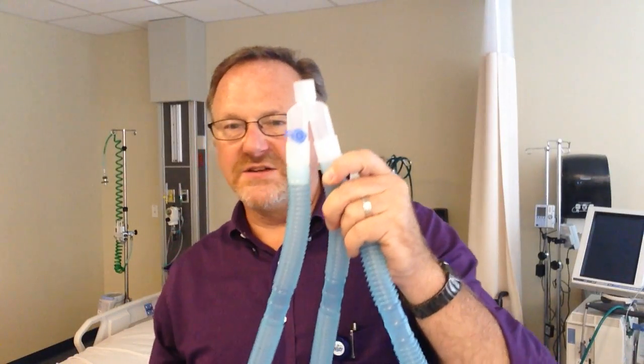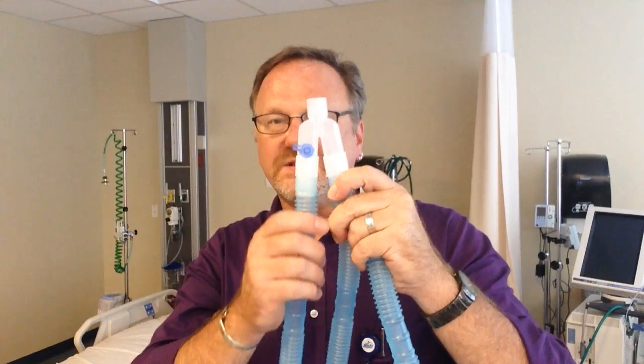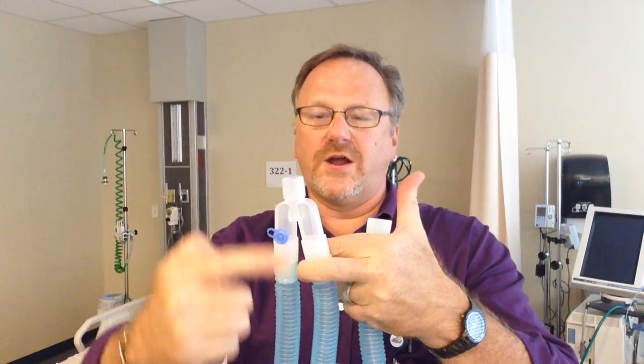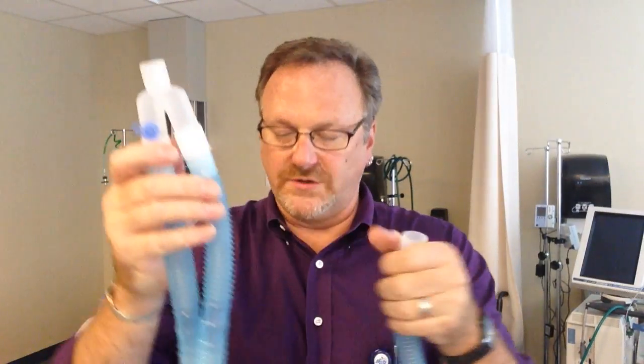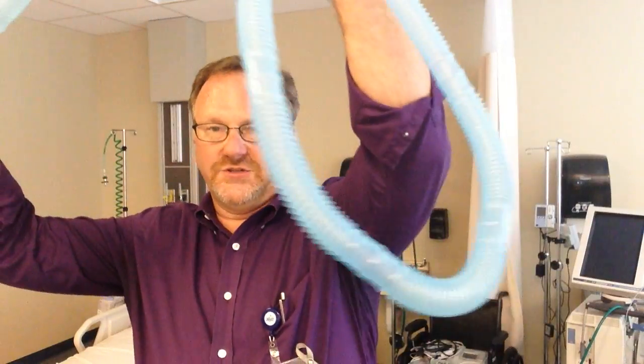So we have positive pressure coming through this circuit. My valve is closed, the air goes into my patient's lungs, the valve opens, the air comes out, my ventilator is no longer delivering a breath. So this is the inspiratory side. This is called the patient Y. Why is it called that? It looks like a Y. It has a tail, or else it'd be a V. So this is the patient Y, or the Y of the circuit, and then it comes down for exhalation.